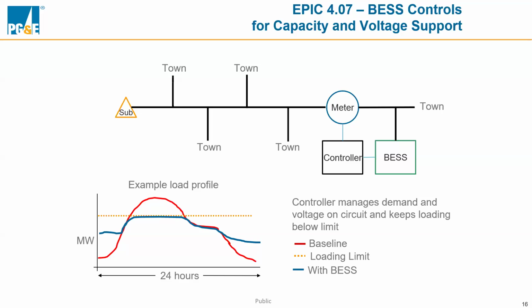This plot shows an example load profile. Based on the hour of the day, the load on the circuit changes. The red line is the forecast baseline in the future state with all these new loads, and the yellow line is the limit. We're using the battery and these new controls to discharge it at peak and keep the load within the limits of the circuit. That's how we're freeing up capacity. That's the start of my project. Thanks.